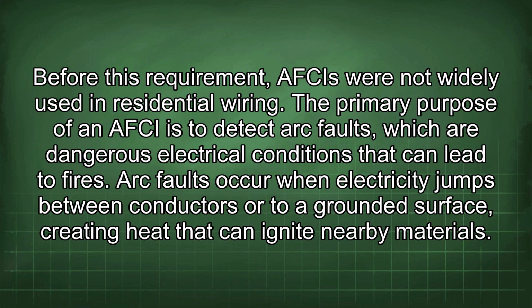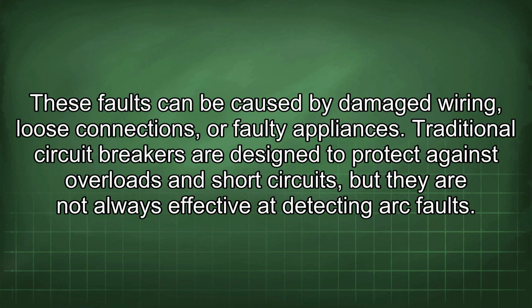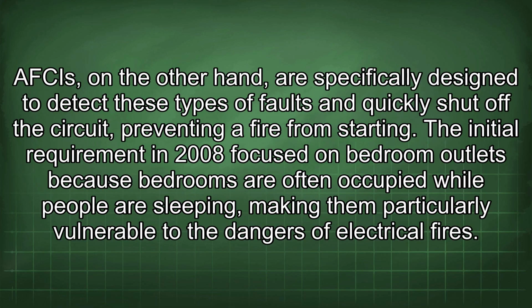The primary purpose of an AFCI is to detect arc faults, which are dangerous electrical conditions that can lead to fires. Arc faults occur when electricity jumps between conductors or to a grounded surface, creating heat that can ignite nearby materials. These faults can be caused by damaged wiring, loose connections, or faulty appliances. Traditional circuit breakers are designed to protect against overloads and short circuits, but they are not always effective at detecting arc faults. AFCIs, on the other hand, are specifically designed to detect these types of faults and quickly shut off the circuit, preventing a fire from starting.